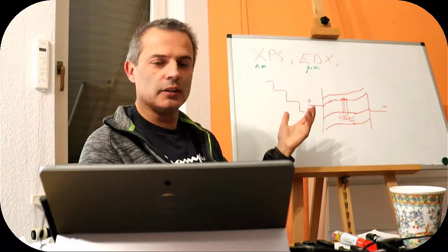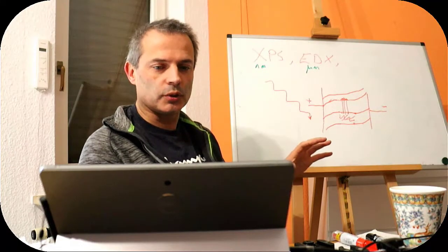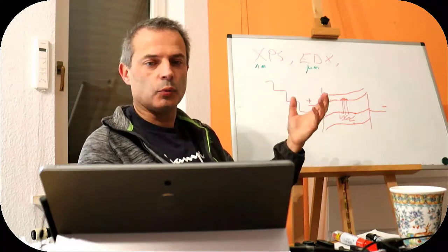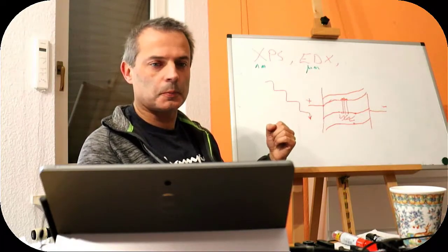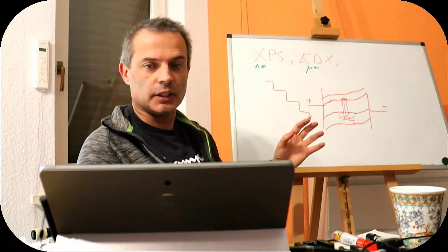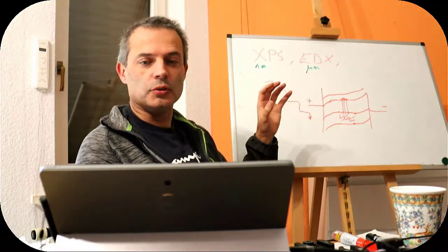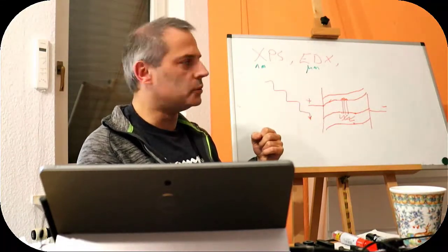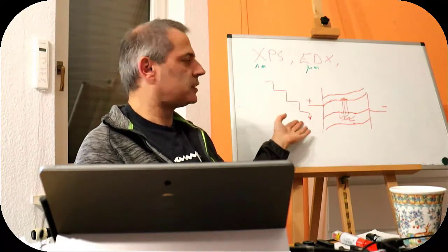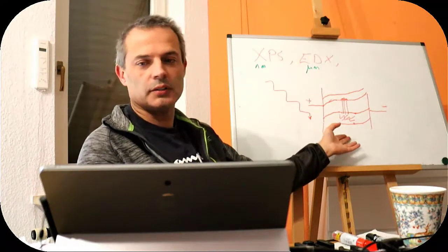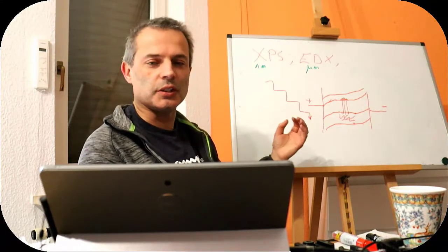But as I said, if we turn it up too much, that becomes a problem. It struggles to deal with it. But if we only have a small number of those events, it can work out how many there are supposed to be because of statistics and then remove those. That allows us to get a comparatively clean spectrum, but it's a complicated task, and when you drive the machine, when you're given one to use, that's one of the issues to deal with: you have to have the correct intensity of photons, otherwise your spectrum becomes less good. It becomes harder to measure.